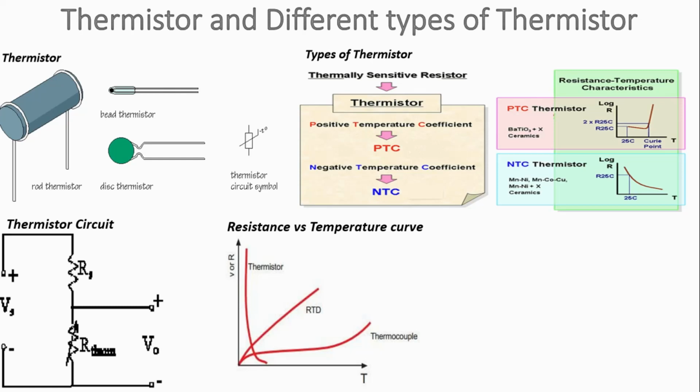A thermistor is a resistance thermometer similar to a resistance temperature detector, that is RTD, and is used for temperature measurement. It consists of a non-metallic resistor that is used as a temperature sensing element. Thermistor is the short form for thermal resistor. The device consists of a bulk semiconductor that acts as a resistor with a high and negative temperature coefficient of resistance, sometimes as high as -6% per degree Celsius rise in temperature.